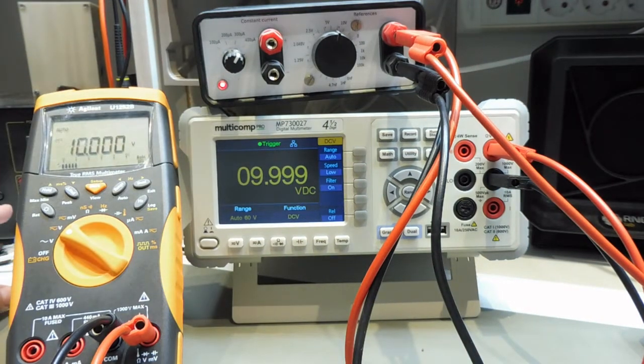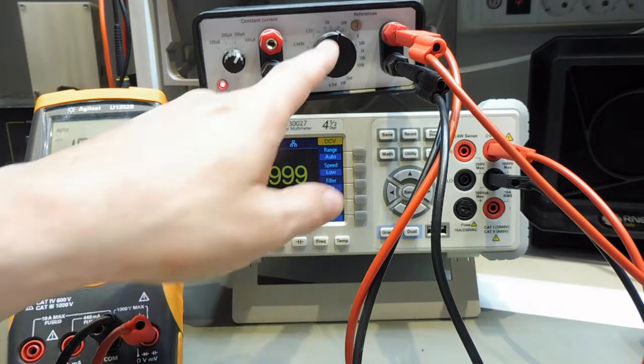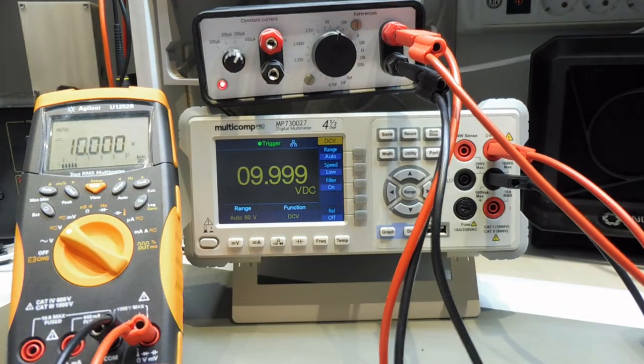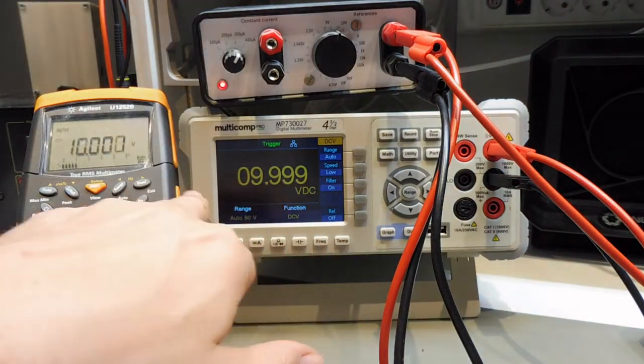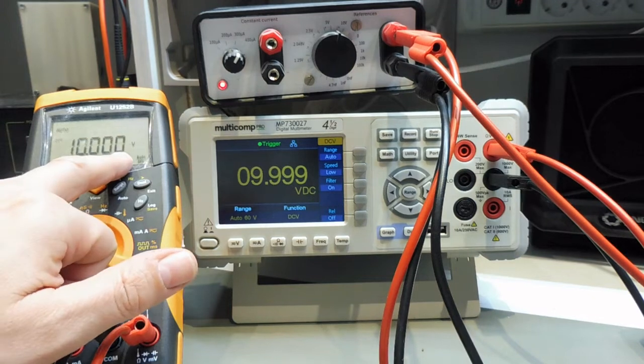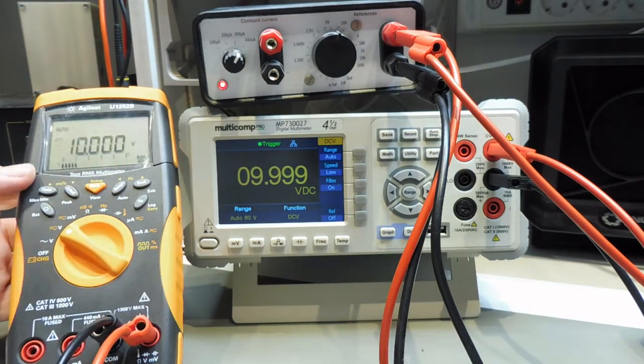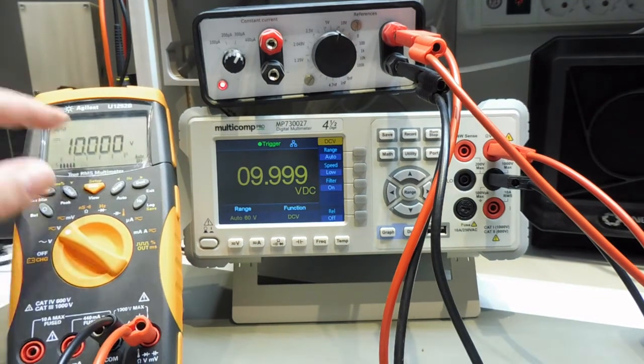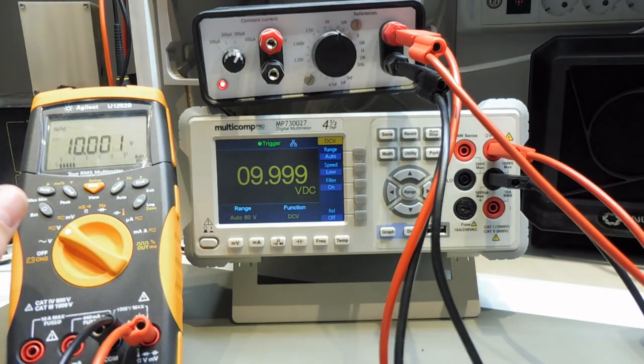So as we can see here, when selecting the 10 volt range, both meters are within 1 digit of accuracy. This one here sometimes jumps to a 1. This one is 1 digit low, but it's still way within specification.